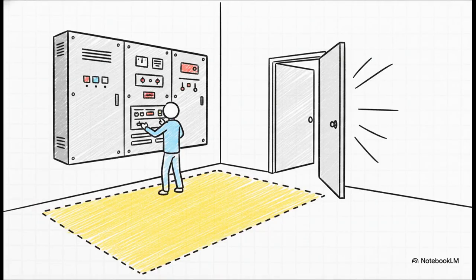Building on that, the accessibility rules are totally non-negotiable. The switchboard has to be entirely unobstructed by the building structure or any fixtures. You need adequate space on all sides so a technician can stand safely, operate the switches, and actually do their maintenance. And crucially, there must be clear emergency exit facilities. A command center is completely useless and honestly a bit of a trap if you can't reach it safely to cut the power, or if you can't escape from it quickly when the equipment itself starts smoking.